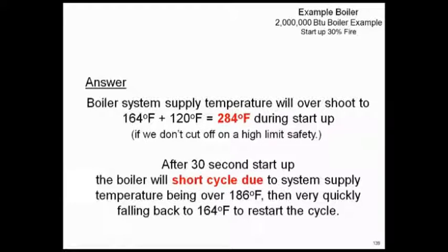Number one question. Second question, how long? Does it take 30 seconds, 40 seconds, 60 seconds? Now I've got BTUs. The next question is, is it having a volume in the system? To be safe, I think we better flow it at a rate enough to make sure we don't hit manual high limit. So if you give me those two numbers, the fire rate of the boiler at startup and how many seconds, I'll tell you what your minimum flow rate is on your boiler, any brand of boiler you want to call and ask us on. It's that simple. Trying to keep you out of trouble.